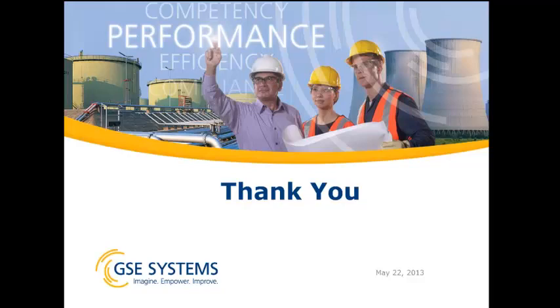Well, I think it has caused us to rethink some of the operating paradigms. For example, some of the things we've seen happening here in the United States, even before regulatory mandate has dictated what will happen, is customers looking at certain plant models, and particularly if their plant simulator had been built many, many years ago, they're looking at more robust electrical system modeling. The practice in the past had often been that we would go without site power for a certain period of time, and your simulator may have to run for 8 or 12 hours. Now we're looking at events where you might have to run your simulator 72 hours. During that process, you have to understand the effect of operating decisions on battery life and electrical buses around the plant, and what decisions you can make to extend the useful life of key equipment.